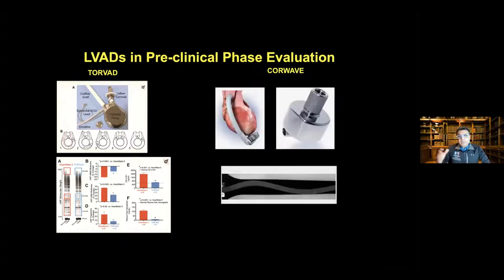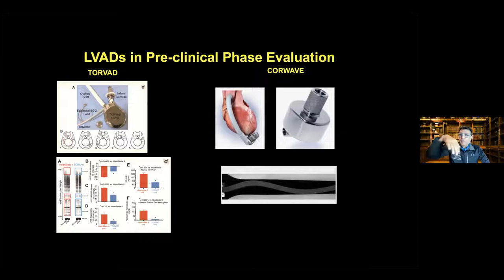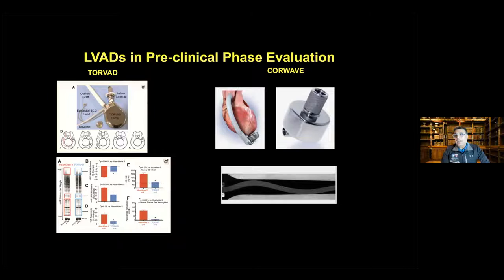A second device, the CorWave, instead of using a rotor has a fishtail-like membrane that propels blood in a synchronous manner, capable of co-pulsation and even counter-pulsation with the heart as physiology demands. One challenge is that it's about 50% larger than even the HeartMate 3, limiting its applicability across all patient profiles. Like the Torvad, the CorWave is about a year and a half to two years away from first-in-human experiments.